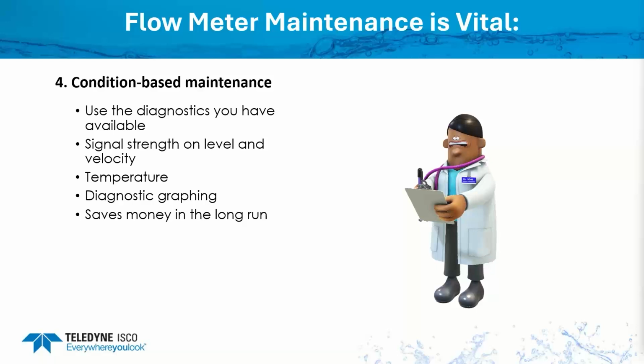So next, I want to stress using condition-based maintenance instead of just a standard operating procedure. A lot of you go out on site every couple of months, every quarter, just because the SOP tells you that's when we have to go out there. And you go out there, you look at it, everything's fine, change the batteries maybe, but you could save money in the long run by actually using the diagnostics.